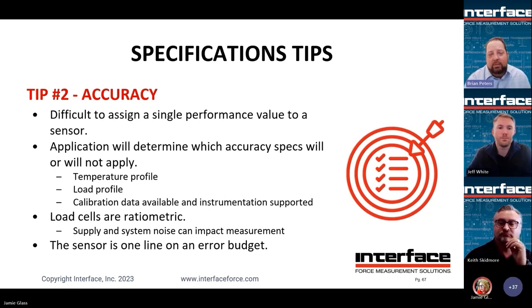What calibration data do you have? If you have either your specific load point or the curve data, then you can take out maybe non-linearity, even hysteresis, from impacting your measurement. So load cells are ratiometric. We mentioned this earlier. Pay close attention to the quality of the excitation that's going to that sensor, because any noise that's coming in on that excitation side is going to now show up in your measurement signal. So pay close attention to that.